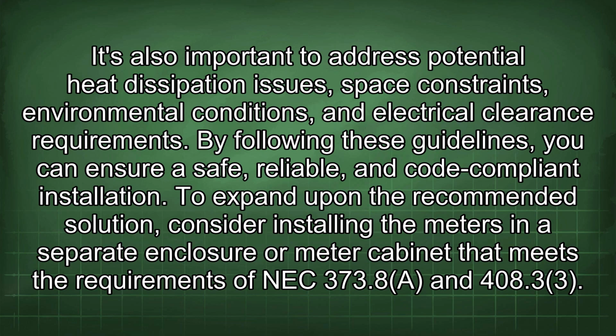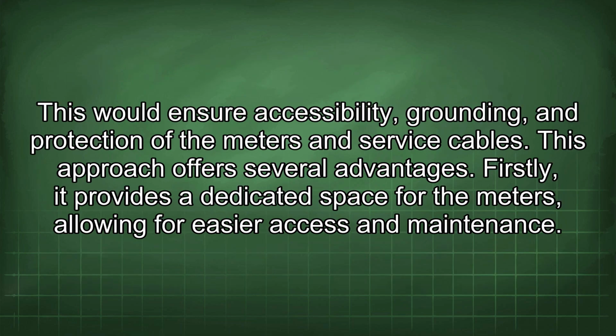It's also important to address potential heat dissipation issues, space constraints, environmental conditions, and electrical clearance requirements. By following these guidelines, you can ensure a safe, reliable, and code-compliant installation. To expand upon the recommended solution, consider installing the meters in a separate enclosure or meter cabinet that meets the requirements of NEC 373.8 and 408.33. This would ensure accessibility, grounding, and protection of the meters and service cables.